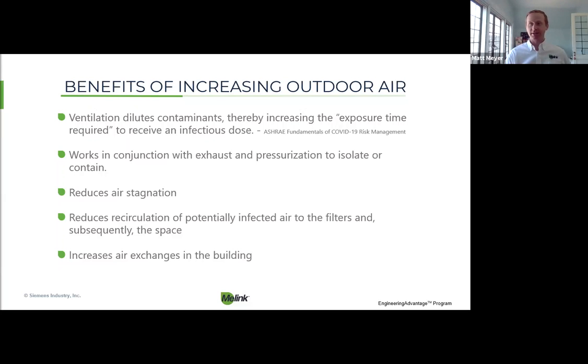So right now they're telling us that if you're in the presence of someone with COVID-19 without your mask on for about 15 minutes, you're considered to have been exposed. What ASHRAE is mentioning here in their fundamentals of COVID-19 risk management is that with increased dilution, you can increase that number from 15 to something closer to maybe 18 or 19. They don't provide any hard numbers or anything like that. It's simply a statement, but it makes sense. So your time in the presence of that infectious dose could go up potentially.